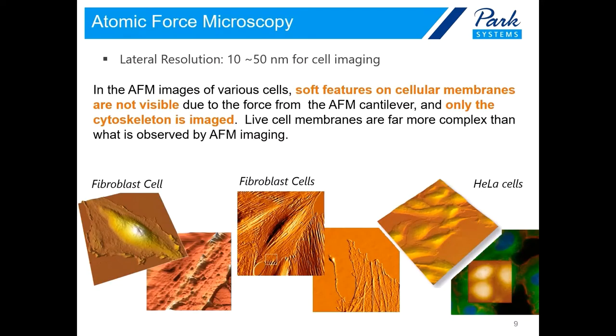Images produced by the scanning probe in AFM can give unique 3D topographical images not obtainable from other optical imaging techniques, and also provide mechanical characterization data for biological samples. There is no better instrument than AFM for measuring single molecular interactions. However, if you take a careful look at AFM cell images, you will see that soft features on the cellular membrane often vanish due to the force of the AFM cantilever. Only the cytoskeleton is imaged by AFM, and the live cell membrane is far more complex than what AFM images show.